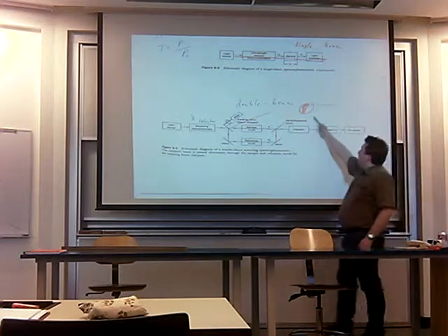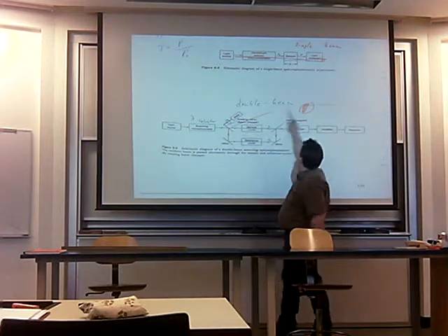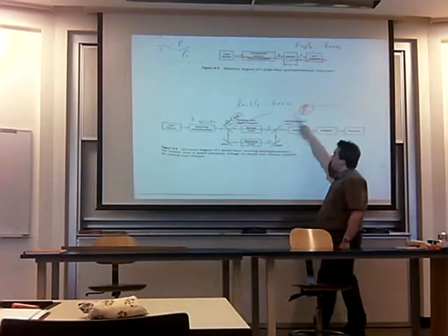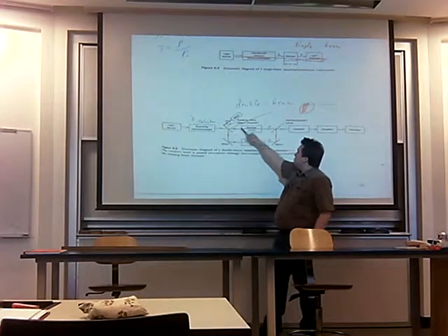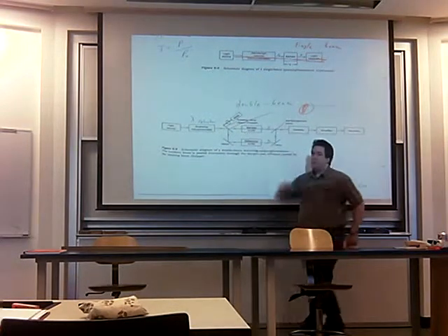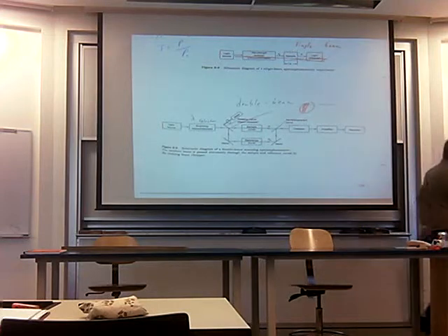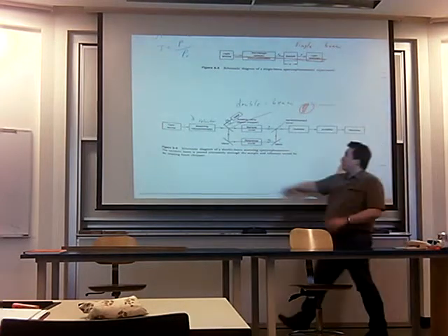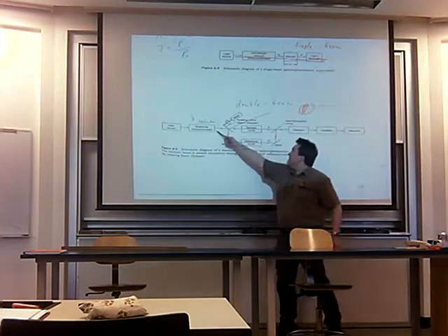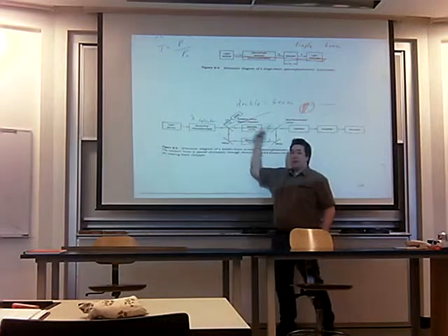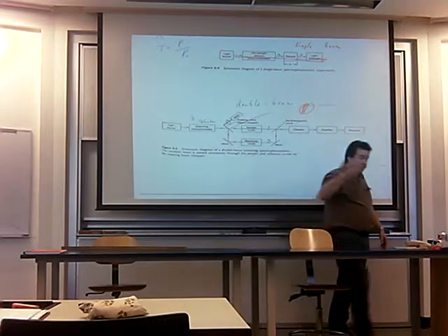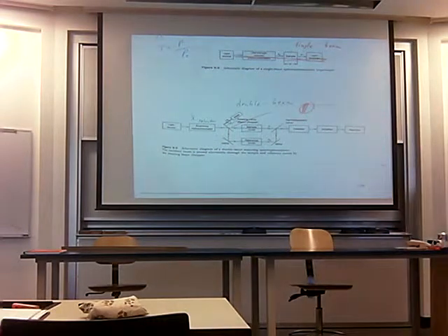When the motor is turned such that the open part is in line, the light goes through and goes through our sample. So as this motor spins, light alternately goes to the reference and then the sample, then the reference, then the sample, several times, usually several times per second, depending on how fast it's spinning.